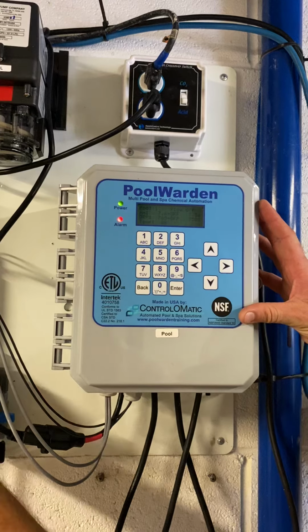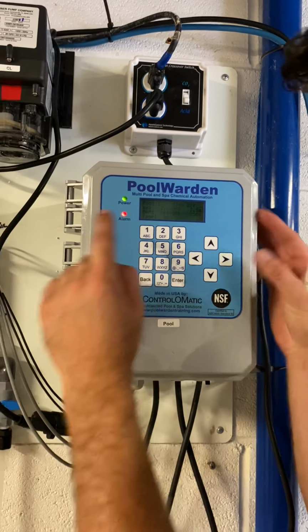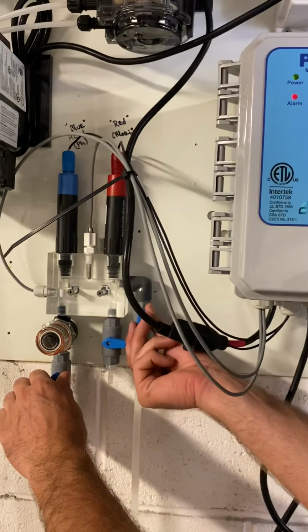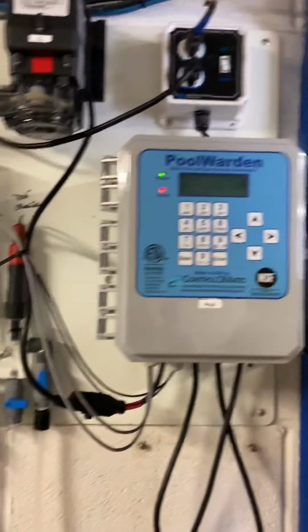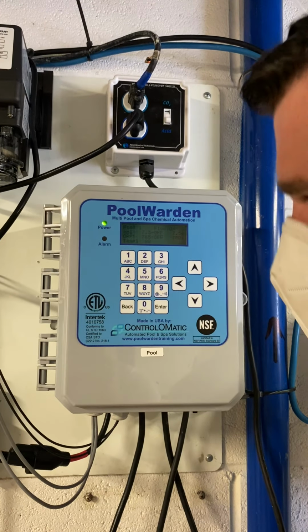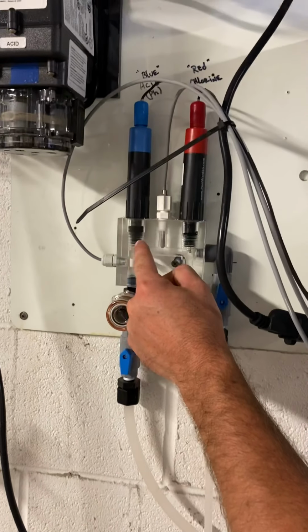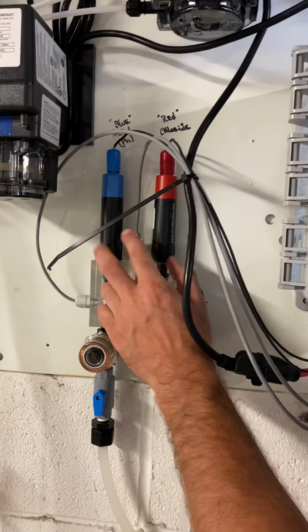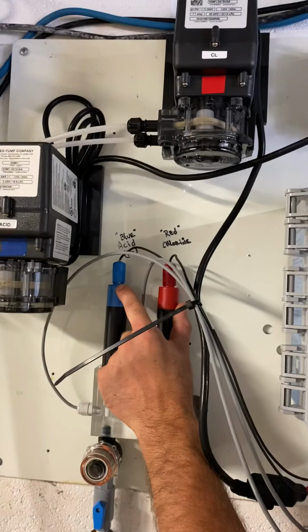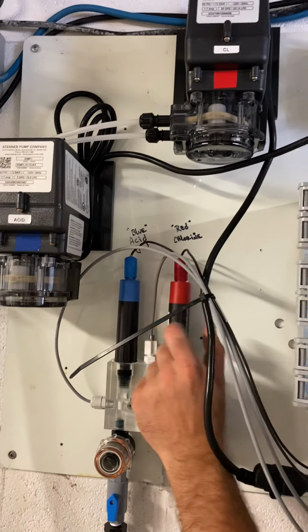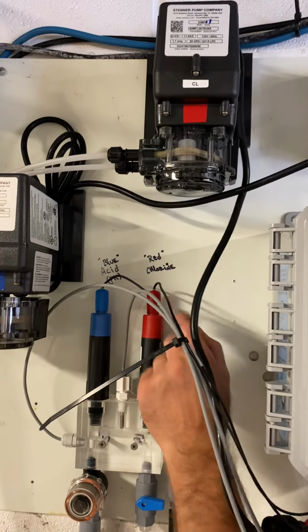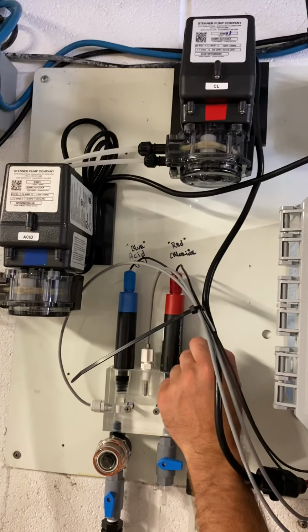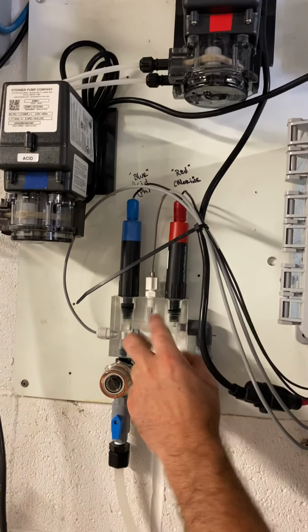This flow cell is tied to this controller. The alarm light is going on because we lost flow. So I'm going to restore flow. And now you see the alarm will disappear. So a sample of water is going into here. It's being drug across these two probes. As you can see, they're labeled up here. So the blue probe is reading the pH. The red probe is reading your sanitizer, okay? It's reading there, and then the sample water is just going right back.